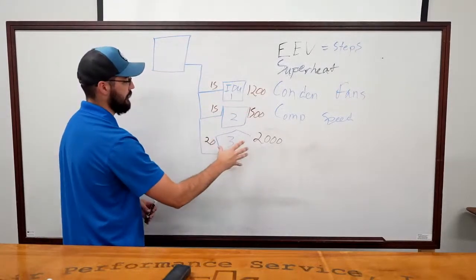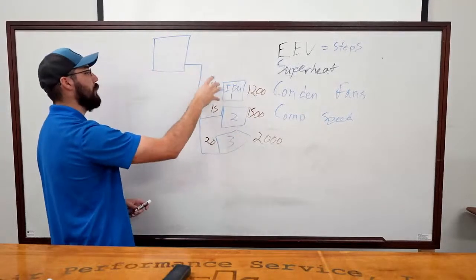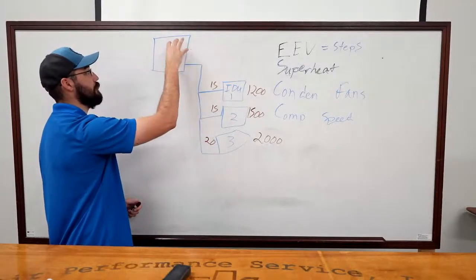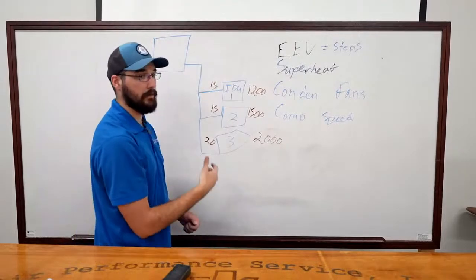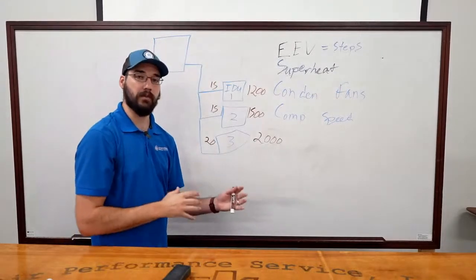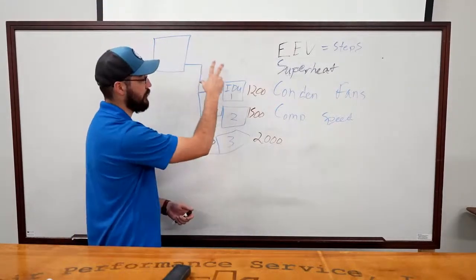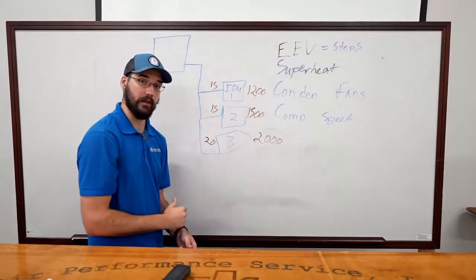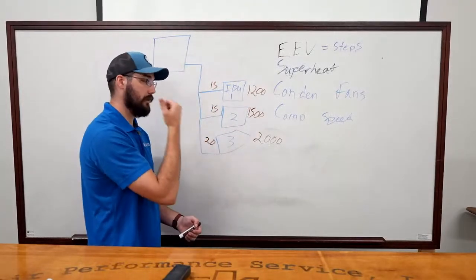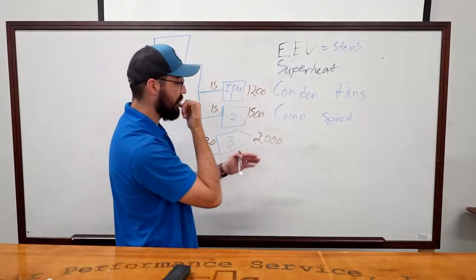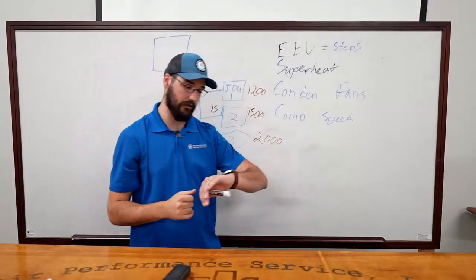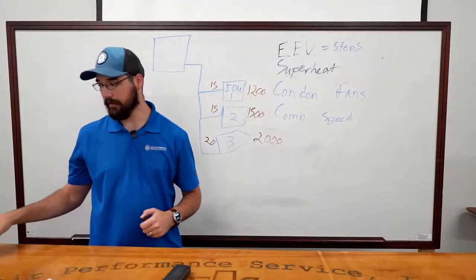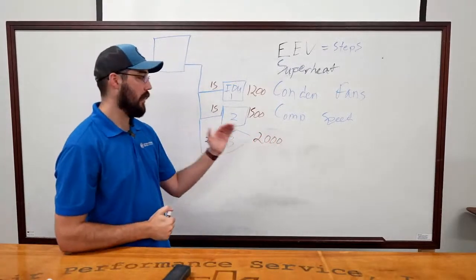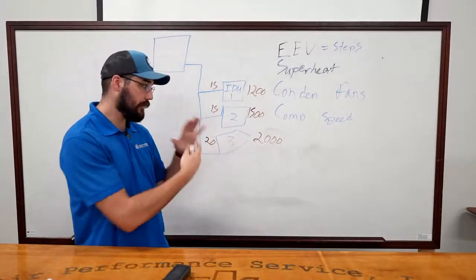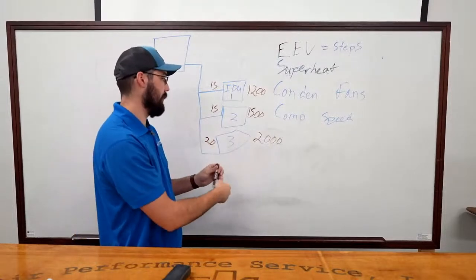At some point in that process, it's going to lead you to needing to connect the laptop to figure out what that specific unit is doing. Then you're going to start to see all these other numbers in the process. That's going to lead you to giving a low charge diagnosis. There's not enough refrigerant in the system to maintain operations. And that is the ultimate problem. It's just not enough charge in there.